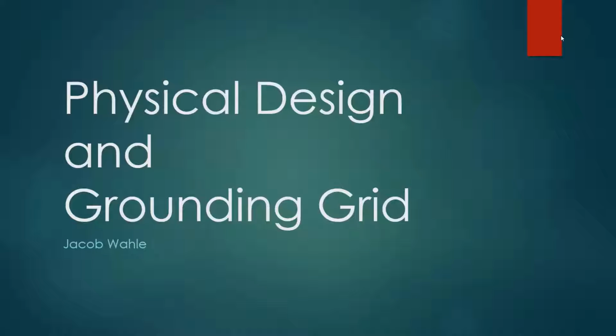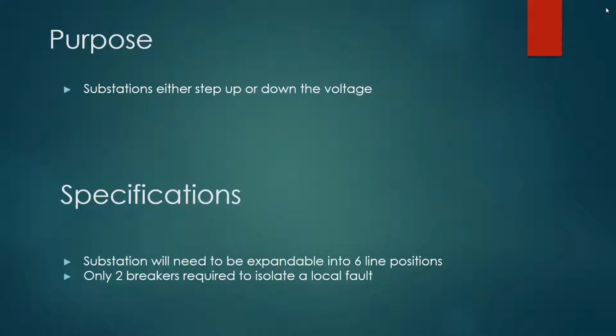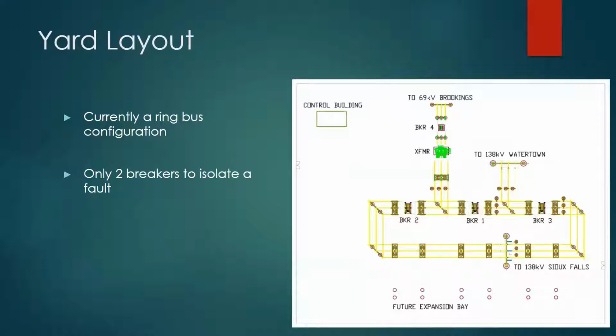Today I'll be talking about the physical design and the grounding grid for the Jackrabbit substation. On the upper level, the purpose of a substation is to either step up voltage or step down voltage. For specifications that will be fulfilled by our physical design, we have substation will need to be expandable into 6 line positions and only 2 breakers required to isolate a local fault. So this is our yard layout.